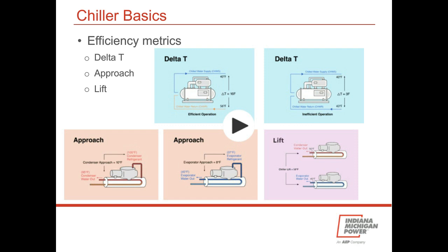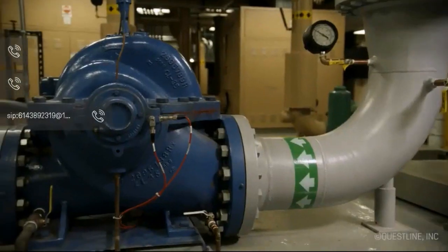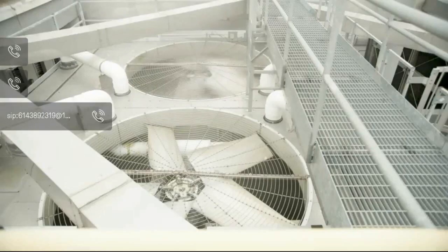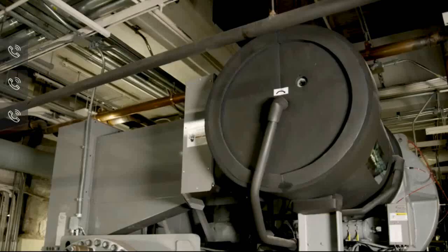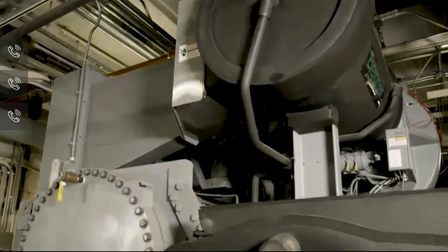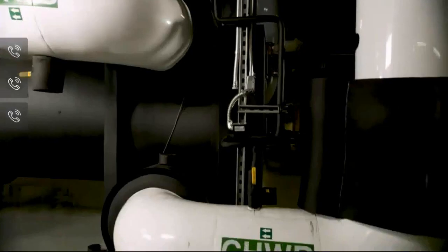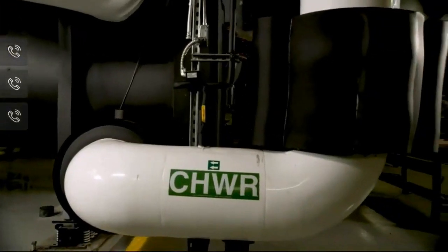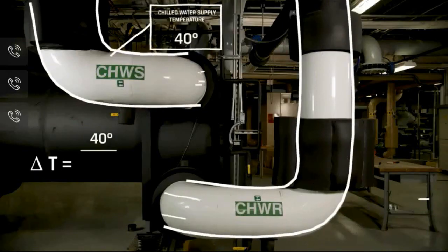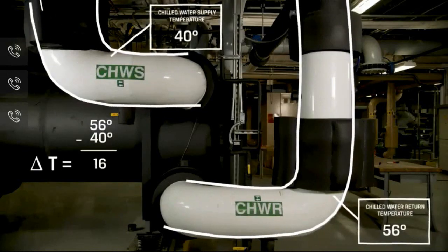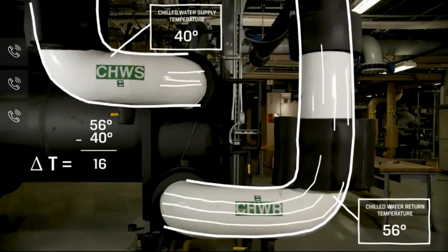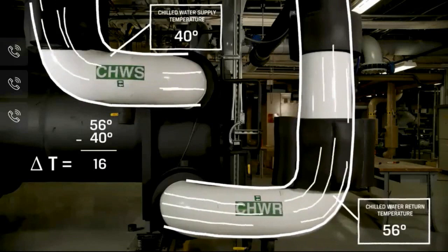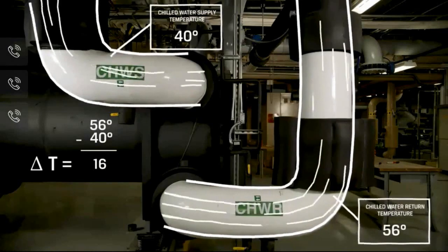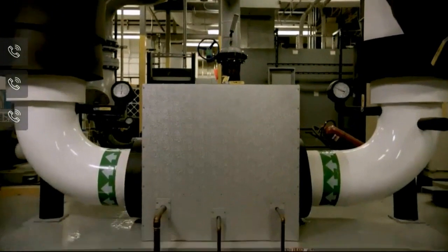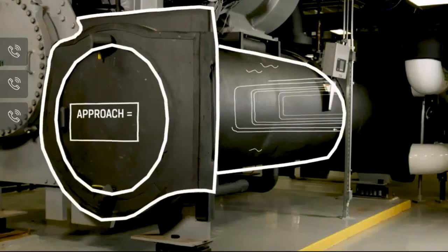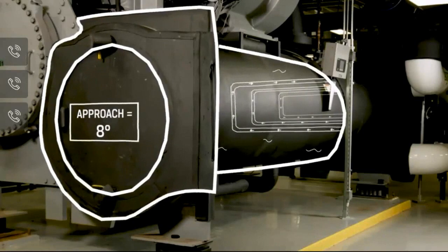Chillers are inherently very complex, and making them efficient can be even more complex. The goal is to constantly balance the cooling tower fan speed and the chiller compressor operation while achieving the lowest kilowatt per ton power draw. There are 3 main reasons for inefficiency with chillers. Delta T is the difference between chilled water supply and return water temperatures. Low delta T forces chilled water pumps to work harder than necessary to produce the needed cooling. More energy is wasted when the operator turns on a second chiller when one properly sequenced chiller would be enough. Approach temperatures, both in the condenser and evaporator, are also important when it comes to efficiency.